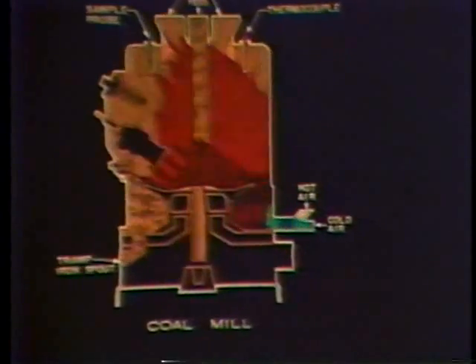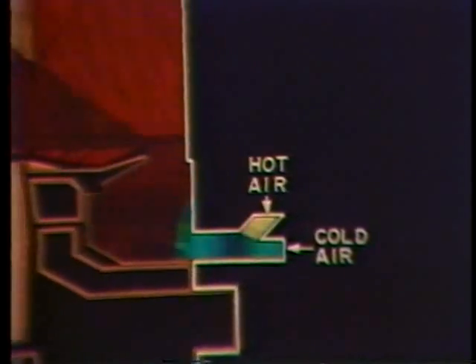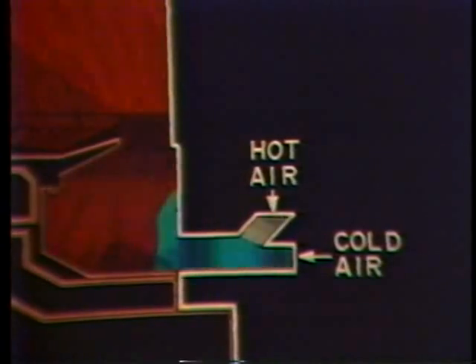Second, the thermocouple indications are masked by process control. As the internally generated heat starts to raise the exit temperature, process control reduces the inlet temperature to keep the outlet temperature constant until the fire has raged out of control and the hot air cold air dampers can no longer overcome the self-heating inside the pulverizer.